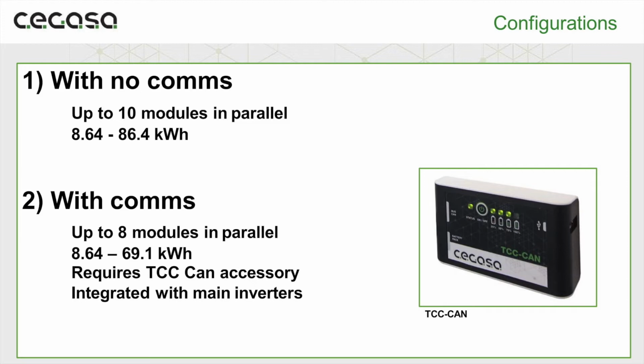As I said, the battery can be set either with communications or without communications. The main difference being that without comms you can go up to 10 modules or 86 kilowatt hours, while with comms it's restricted to 8 modules, around 70 kilowatt hours.